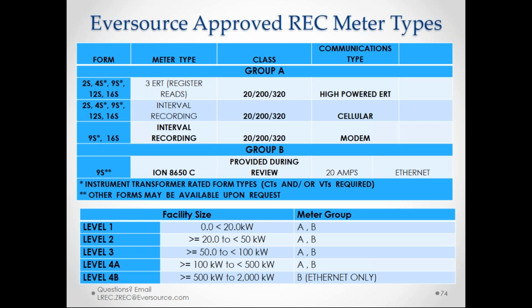In most cases, for anything under 500 kW, that will be a ERT meter, which is a high-powered radio frequency meter. That's why we typically insist the meter be installed in an exterior ground level location, so if it needs to be accessed by us for some reason, we can, and so the radio frequency reading from the meter can easily be accomplished by our drive-by vans, same as with our billing meters.